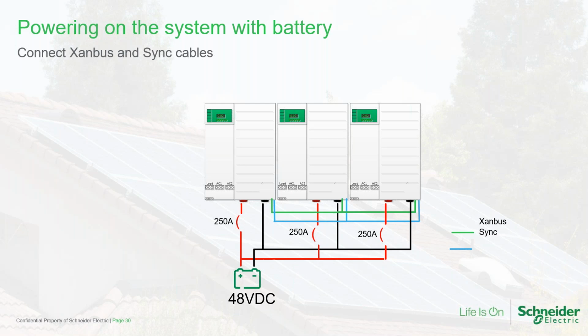Now that all three XW Pros have had the transformer wires moved and the jumpers installed, connect Xanbus and Sync cables. These are just simple Ethernet cables. Then energize one XW Pro at a time with battery voltage. Each XW Pro will have a dedicated 250 amp DC breaker in the PDP. The three-phase system should have a common battery bank.